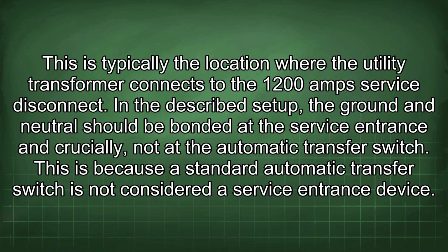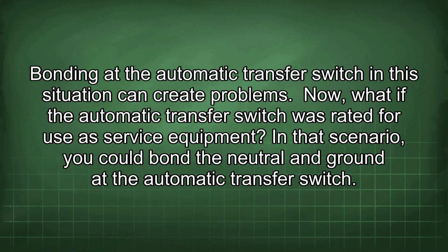In the described setup, the ground and neutral should be bonded at the service entrance and crucially not at the automatic transfer switch. This is because a standard automatic transfer switch is not considered a service entrance device. Bonding at the automatic transfer switch in this situation can create problems.